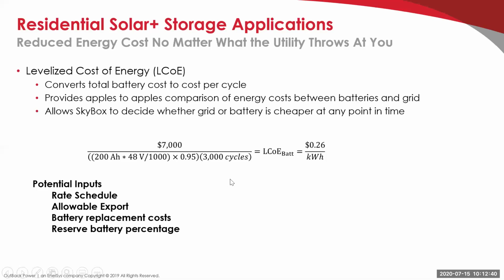The Skybox at some point will probably be our biggest seller, but it's still relatively new and people are getting used to installing it. One thing that's cool about the Skybox is the simplicity of programming it to save the customer money. The inputs are: rate schedule, which can be variable like San Diego Gas and Electric, or flat like most other places in the country; the allowable amount of export; the battery replacement cost, basically the cost of the battery bank; and the reserve battery percentage, which means the depth of discharge of that battery bank.